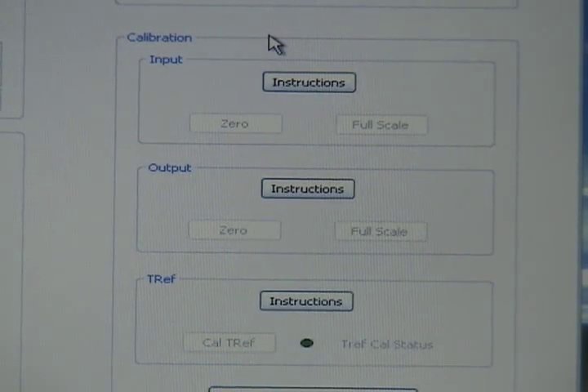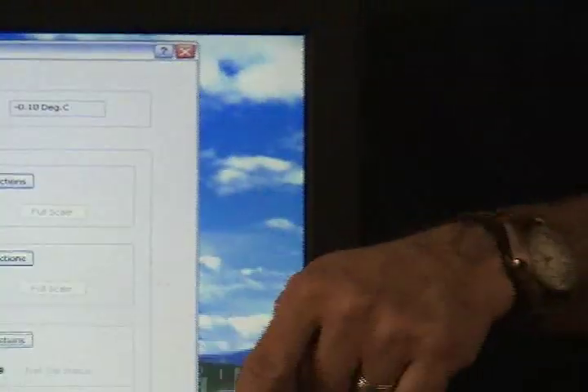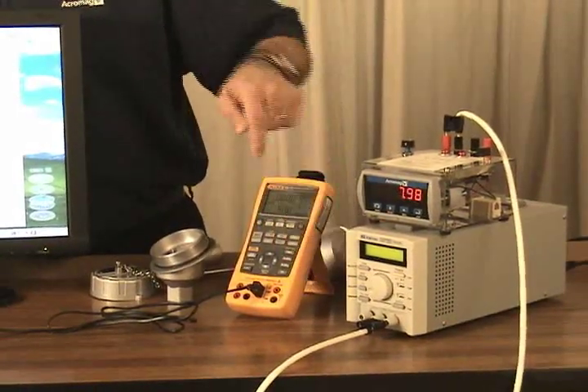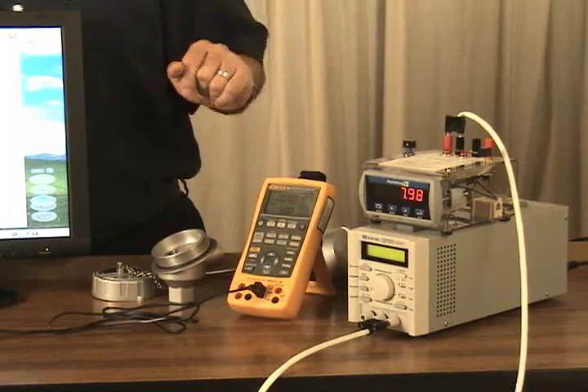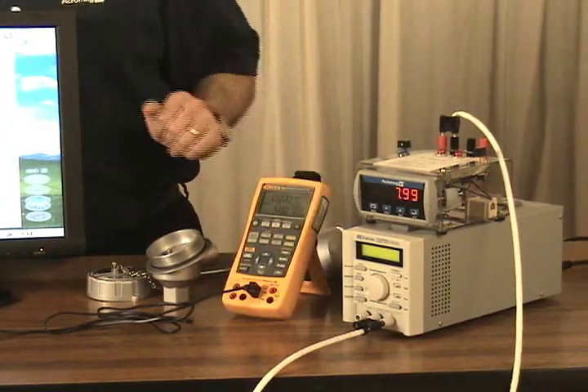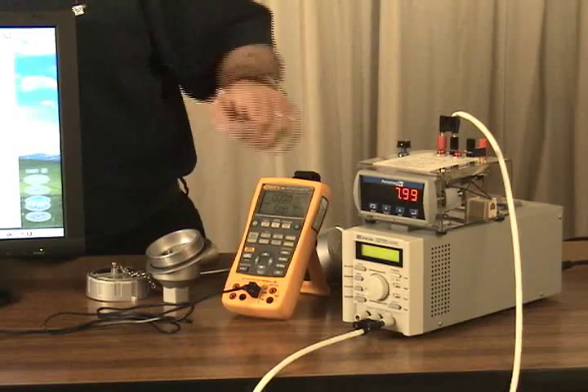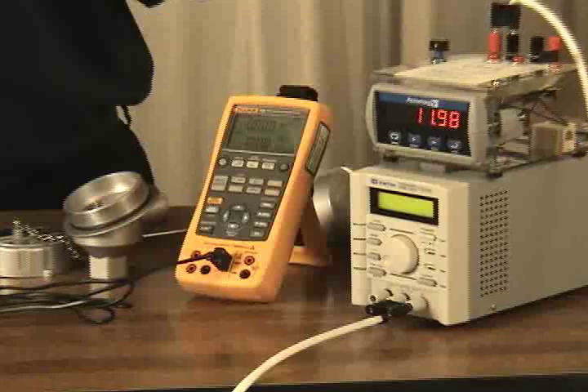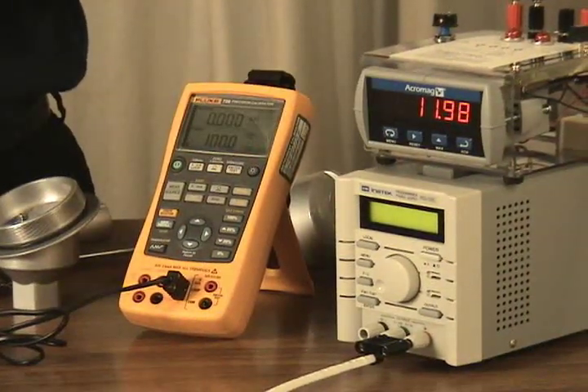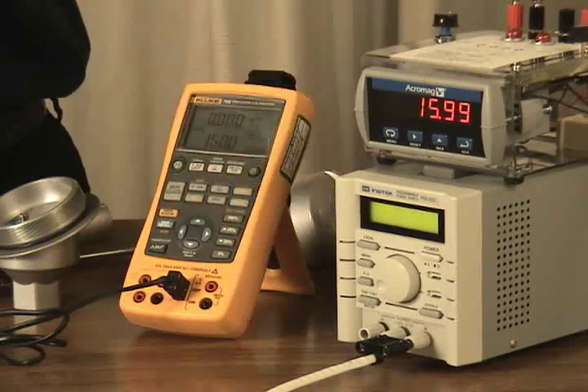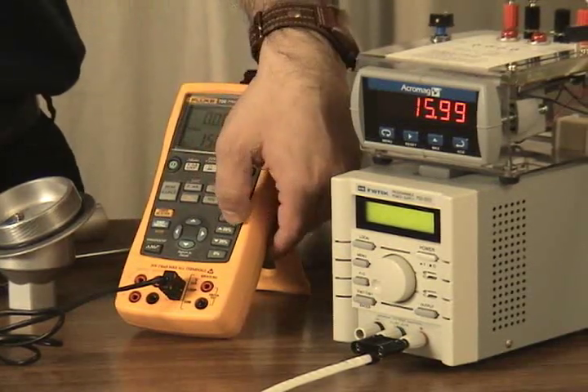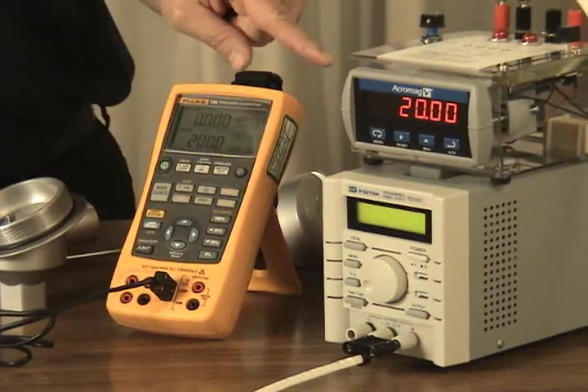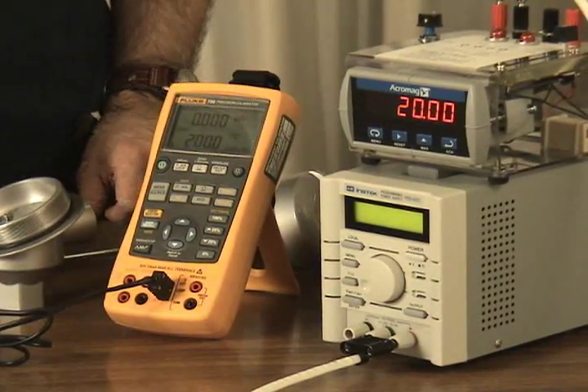Okay let's see how we're doing. Right now I've got 0 degrees C going into the unit and I've got 4 milliamps coming out which is what I expect. If I step through and I put 50 degrees C in my output should be close to 8 milliamps and it is. If I step up to 100 degrees C I'm at 50 percent of my input range, my output's at close to 12 milliamps. And if I go to 75 percent of my input my output's at 16 milliamps. And if I go to 100 percent of my input, 0 to 200 degrees C, you can see I'm at 20 milliamps out.